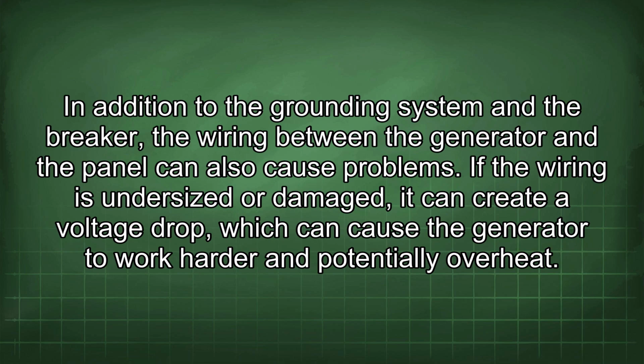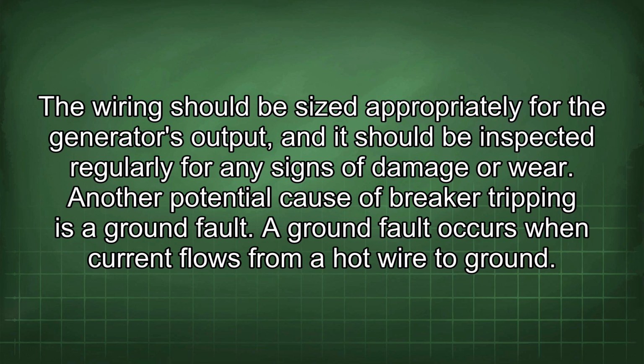In addition to the grounding system and the breaker, the wiring between the generator and the panel can also cause problems. If the wiring is undersized or damaged, it can create a voltage drop, which can cause the generator to work harder and potentially overheat. The wiring should be sized appropriately for the generator's output, and it should be inspected regularly for any signs of damage or wear. Another potential cause of breaker tripping is a ground fault.